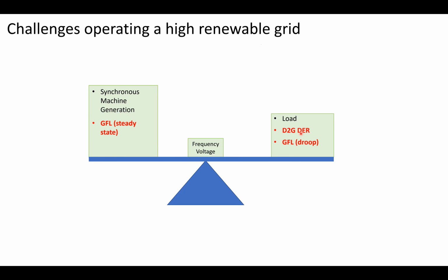But then the additional thing that's thrown a curveball for us has been the inverters operating in grid following mode, but also operating in droop. And the reason I put that on this side of the seesaw is there's a delay in the grid following response of the inverters while they're operating in fast frequency droop response. And that delay actually causes an imbalance in our frequency on our grid.